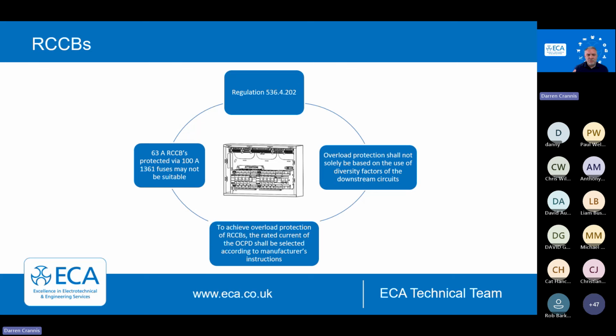You might have seen them before where they had two 63 amp, 30 milliamp RCDs in, and what you might see is manufacturers maybe changing them to 80 amps or 100 amp. And it's just asking that the RCCB has no overload. So it's really looking at what's upstream of that. So either that will be the cutout fuse, or if it's in a commercial environment, it might be the circuit breaker beforehand. So just consider those requirements when you're using split load boards. And it's really important here that the manufacturer's instructions are followed. We're not overloading those devices. We are using the devices in the set way, and we're keeping those loads distributed across the 2 or 3 RCDs that are in that board.